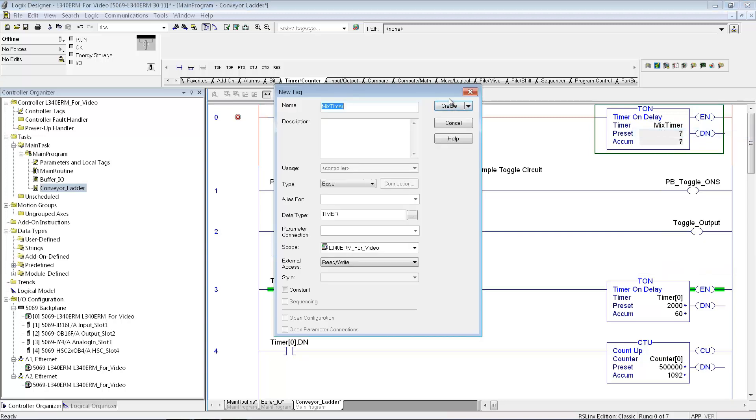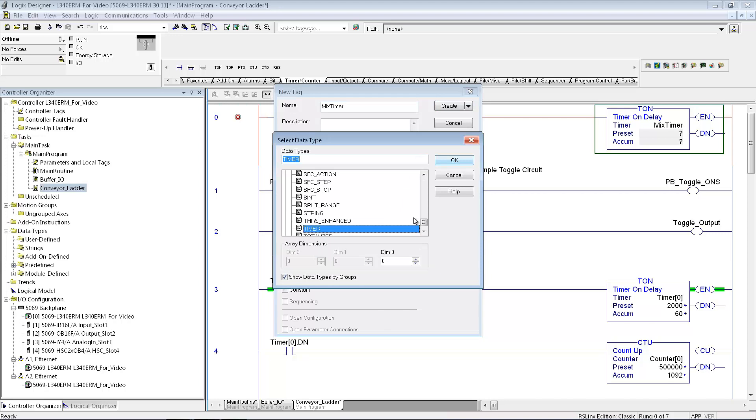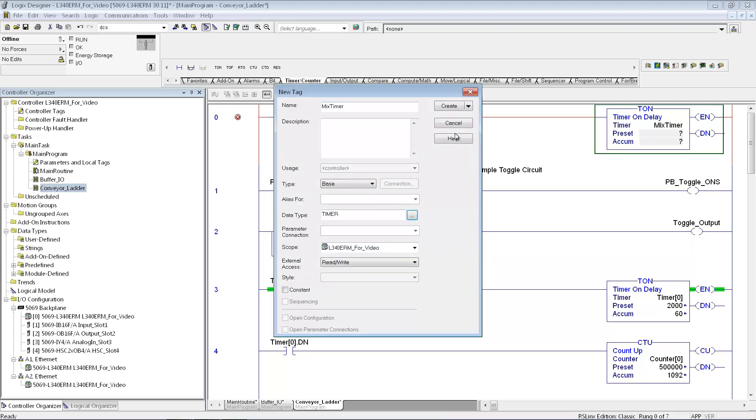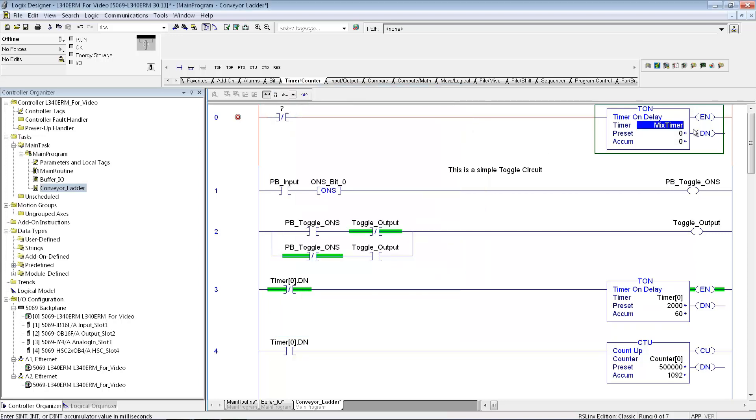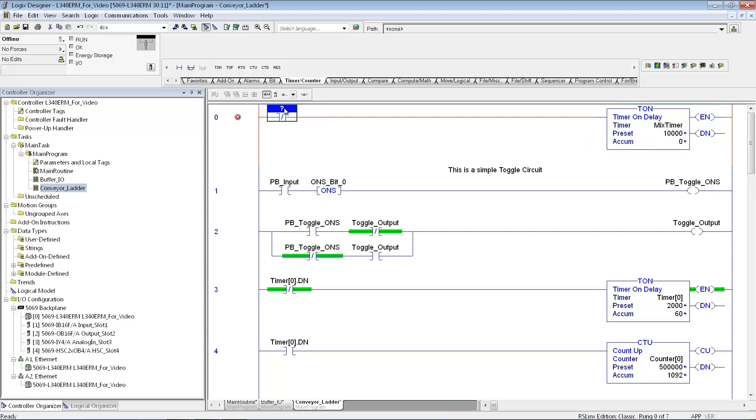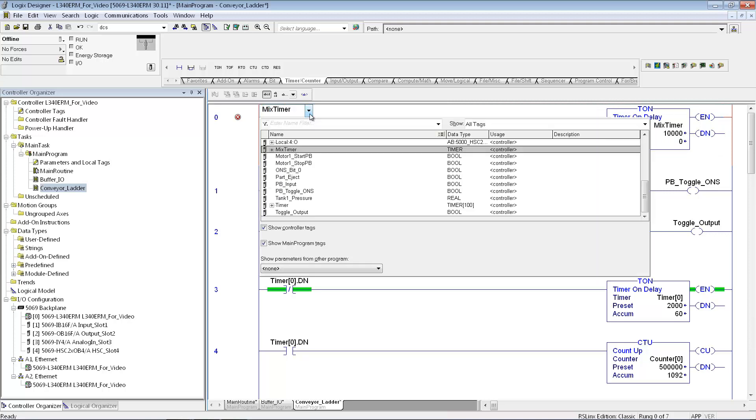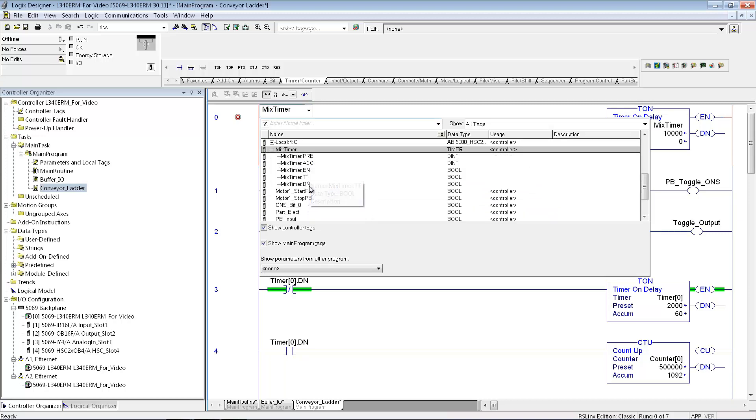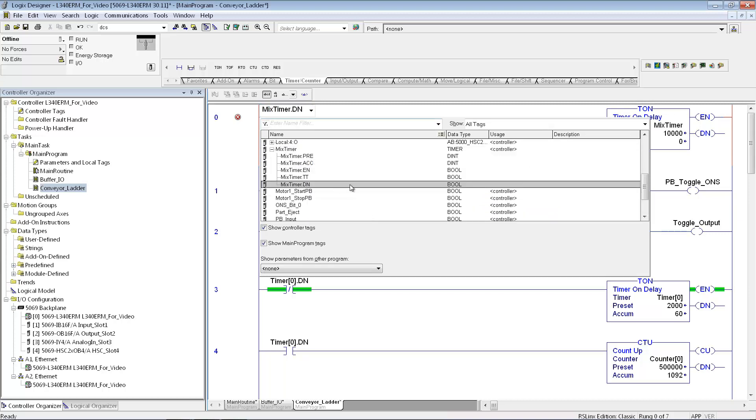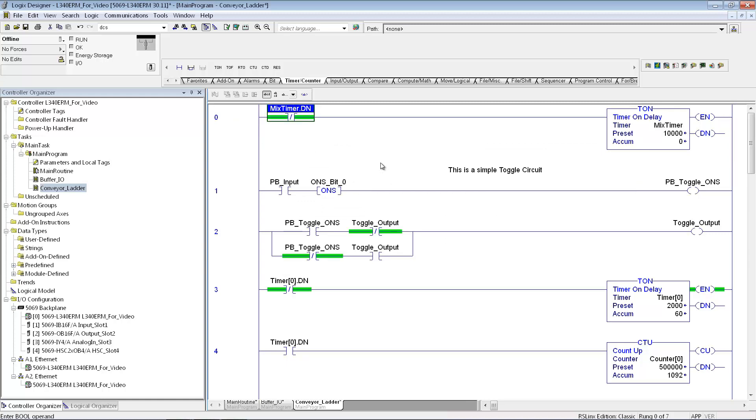All of the timers in the ControlLogix are based on milliseconds. So if I put in a value of 10,000, that's 10,000 milliseconds. So I set up my timer. I'm calling it mixed timer. I need to create that. So I right click on that. Mixed timer, it's going to be of type timer. I can make an array of timers if I wanted to. In this case, I'm just going to make one. Say create. And now I can put in whatever preset I want. So if I want it to be a 10 second timer, I'll put in 10 seconds. Now here, if I just want it to be a free running timer, I'll just say mix timer. And then if I hit the little pull down, it will have the done bit right there. And now I've just made a simple free running timer in this case.